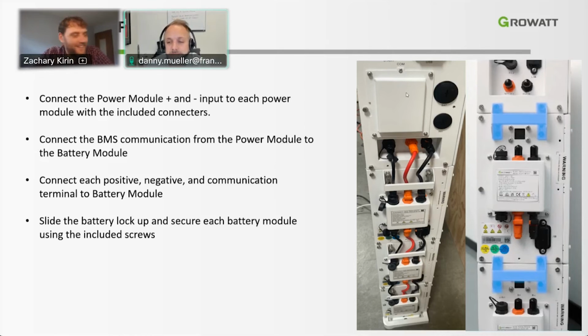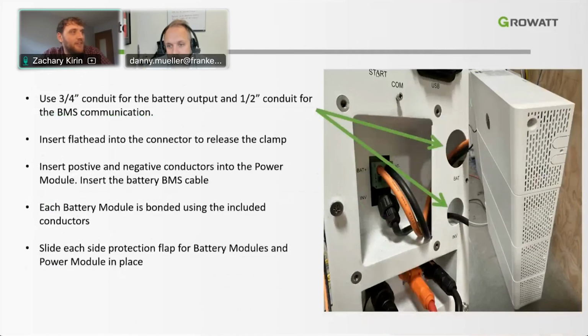Yes, so each of those battery modules are easily connected here, and there's just a locking mechanism to screw each of those locking mechanisms to each battery module, and then the top module as well. So this is how everything is nice and secure. Everything stays together. There's no worry about anything tipping over or anything coming loose in that sense. Everything is locked together. You can use a 3/4 inch conduit for the battery outputs and either a 1/2 inch conduit for the BMS output if you choose.